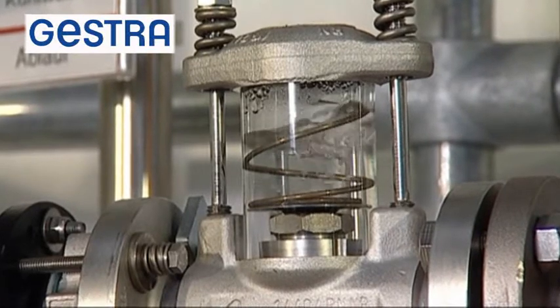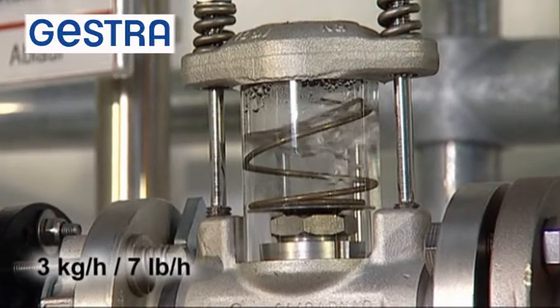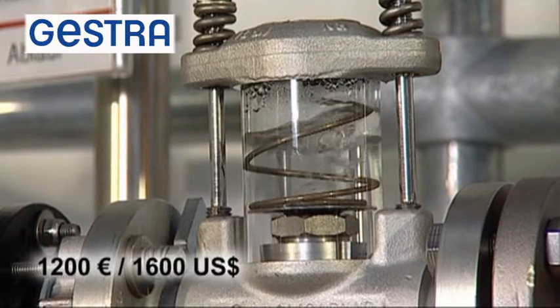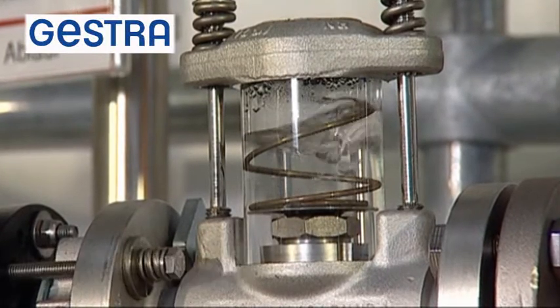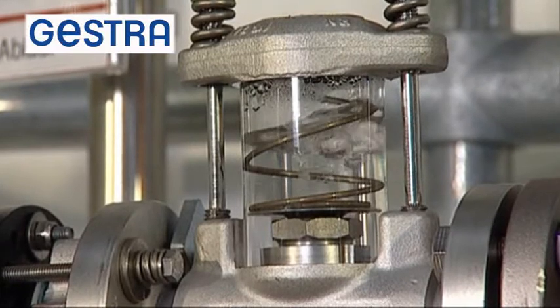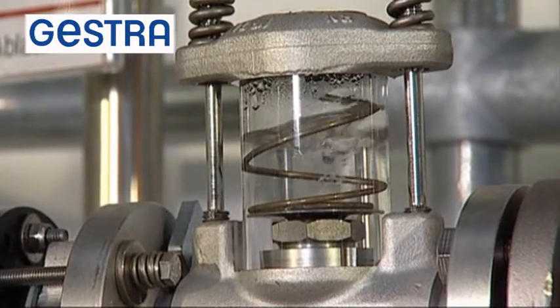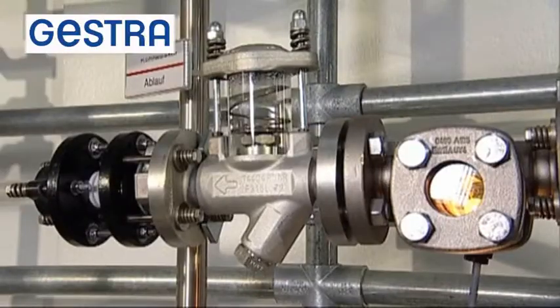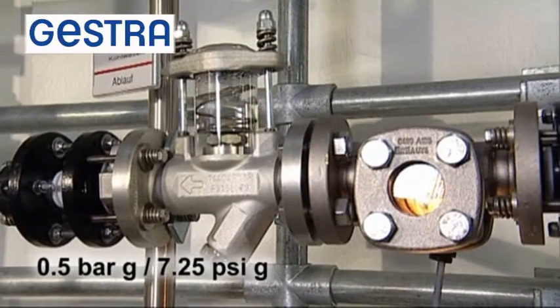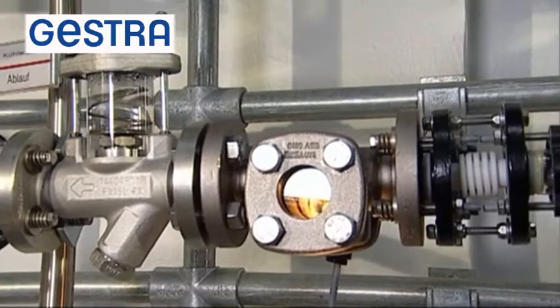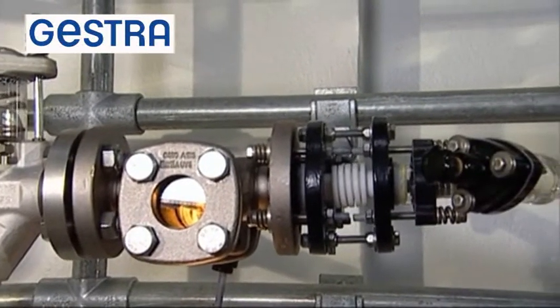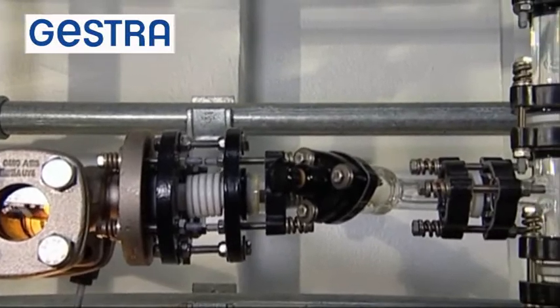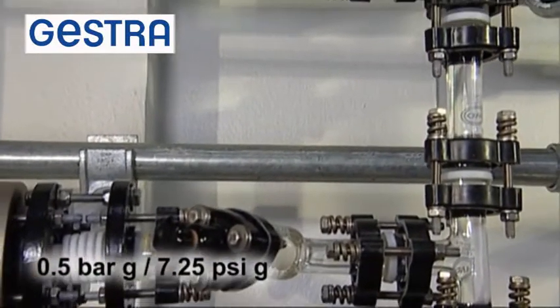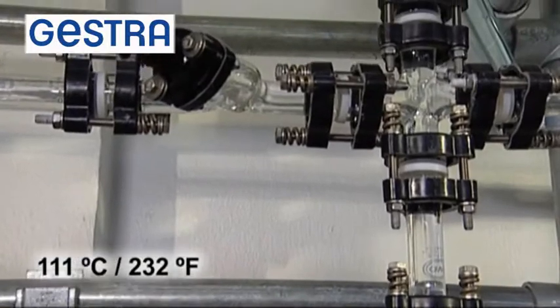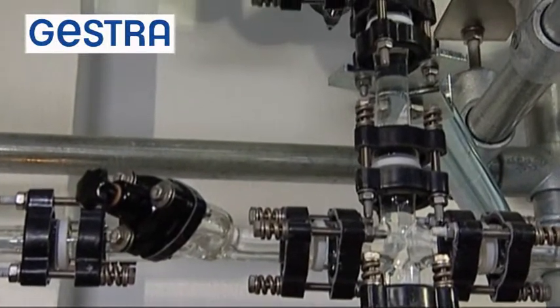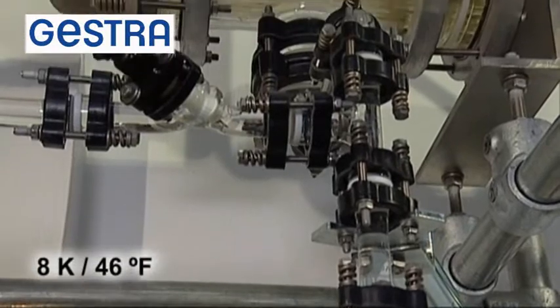If a steam trap causes a continuous steam loss of approximately 3 kilograms per hour, this can result in added costs of 1,200 euros per year at today's energy prices. This sum exceeds the price of a new thermostatic steam trap many times over. The operating pressure is reduced to 0.5 bar G. Owing to the reduced boiling point, the steam trap closes initially. Once the pressure and temperature have settled down to the values 0.5 bar G and 111 degrees centigrade, the membrane steam trap opens as soon as the undercooling reaches 8 Kelvin.